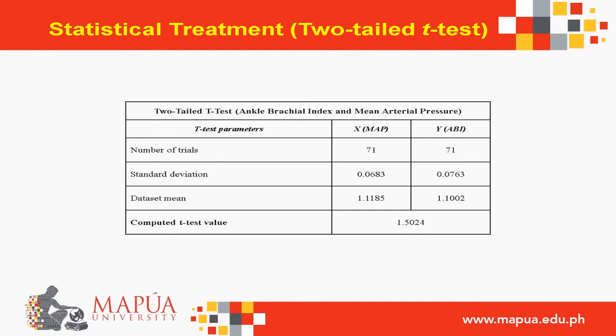This slide shows another two-tailed T-test, but this time for MAP and ABI, since these two are the main values used to determine if a patient has PVD or not. For this T-test, we used 71 trials and the computed T-test value is 1.5024. Again, the computed T-test value is less than the critical value, so there is no significant difference and the two values are comparable to each other. Overall, this basically means that the prototype is, as expected, accurate.